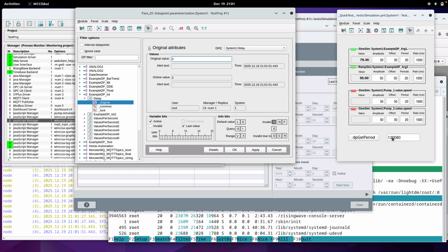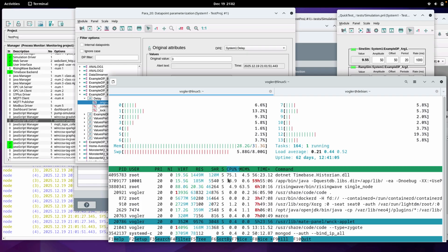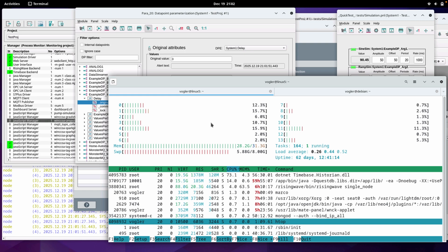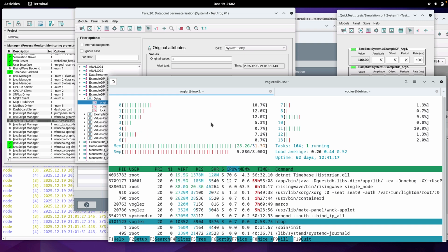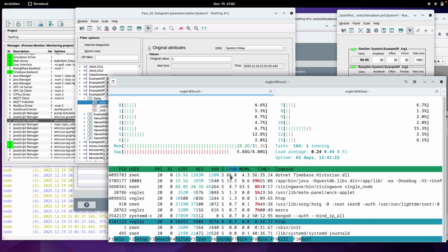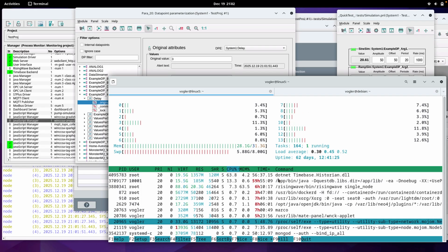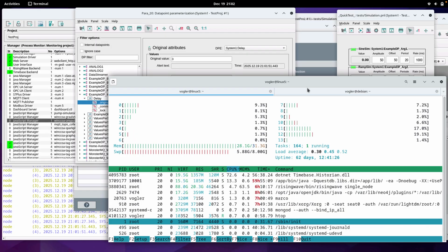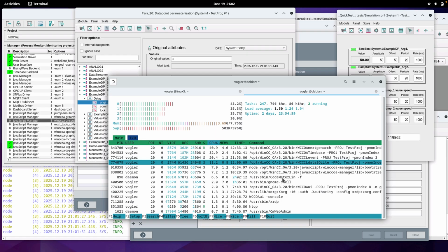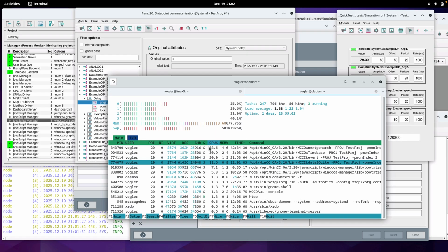above the 100,000. So WinCC OA is now handling 100,000 value changes per second, coming in from two managers. This is like getting the data from PLCs, and then we are distributing the data, in that case also to our logger, and all of the data is logged to the historian. We see now it is using a little bit more CPU, but also not that high for 100,000 value changes per second. And also the WinCC OA system is running under a normal condition, let's say.